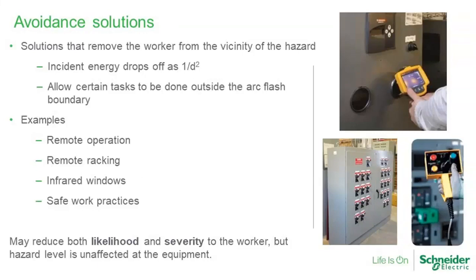Third one, avoidance: solutions that remove the worker from the vicinity of the hazard. We talked about how working distance affects the calculation. It's a little bit of an approximation, but energy falls off roughly as 1 over distance squared as you move away from the source of the arc. So if we can do certain tasks remotely, remote operation of breakers, remote racking of withdrawable circuit breakers or contactors, even outside the arc flash boundary where the energy will be less than 1.2 calories, we have done a lot to protect the worker.